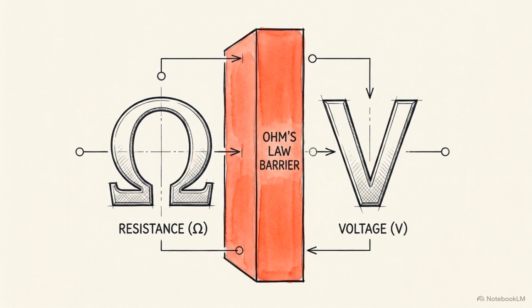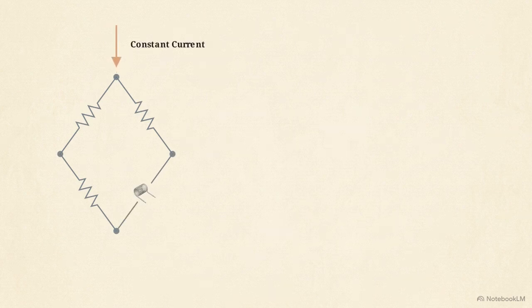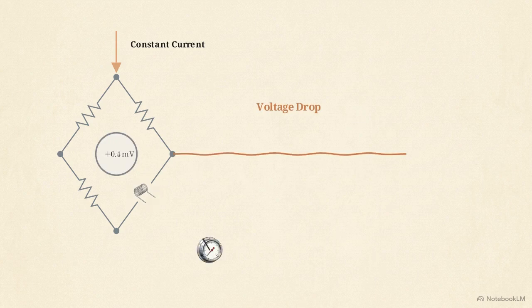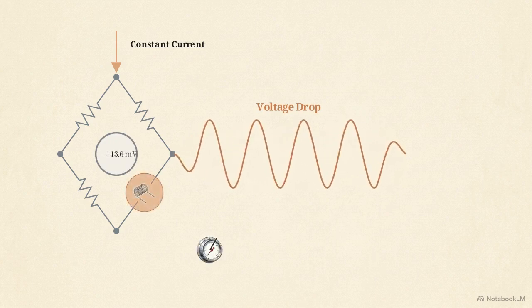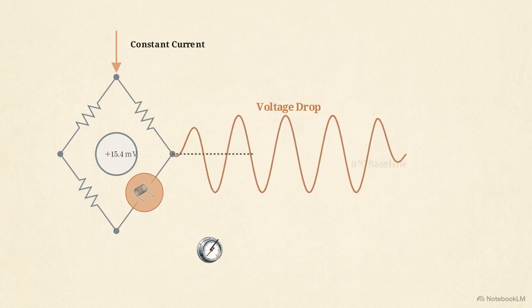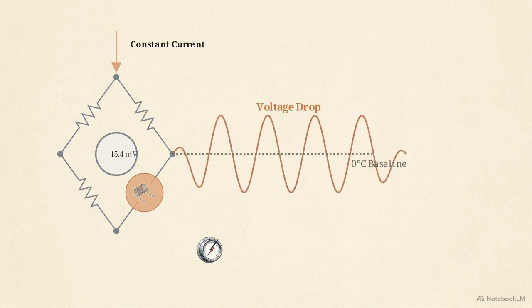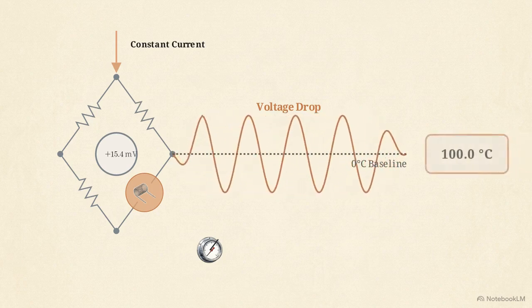The platinum coil perfectly fulfills the role of a sensor by changing its physical resistance in response to heat. But physical resistance itself is not a readable voltage signal. Wired into one arm of a Wheatstone bridge, the passive RTD receives a constant current to generate a measurable voltage drop. As temperature varies, resistance shifts, unbalancing the bridge. Comparing this current resistance to a 0-degree baseline outputs a precisely calibrated temperature reading.